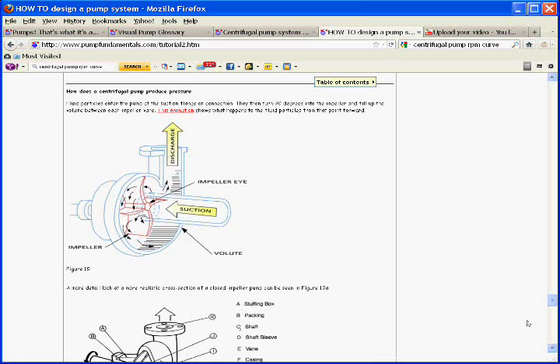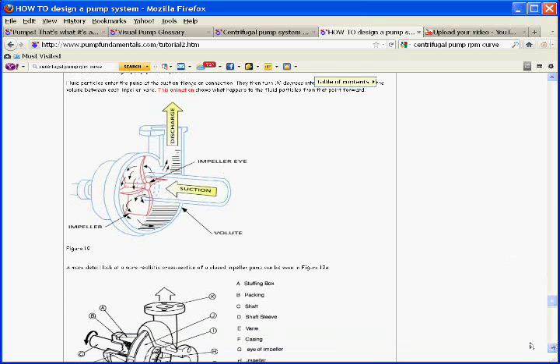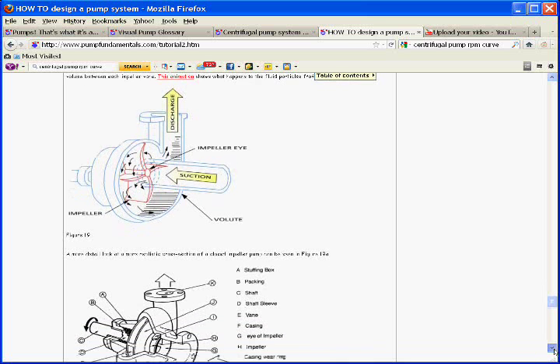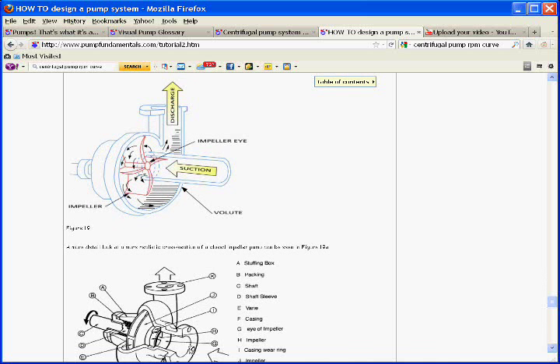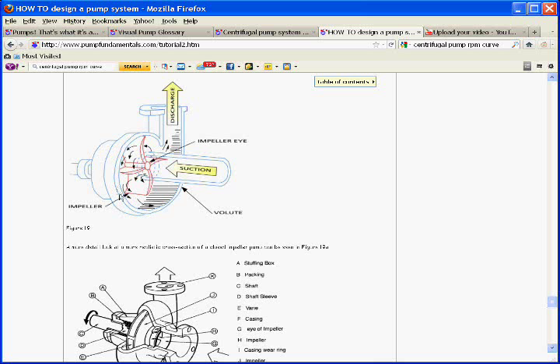So a centrifugal pump consists of a rotating impeller. The liquid comes in at 90 degrees to the pump. It enters the impeller, which is right here. The liquid comes in and then comes onto the impeller blade and changes direction, being forced by the impeller blade. The liquid is being forced through this cavity between two blades and pushed out radially into the casing and then out to the discharge.